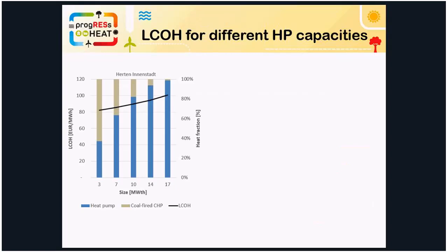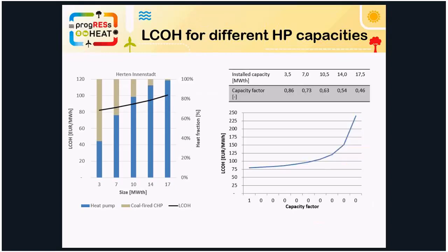We can see that as we increase the size of the heat pump, the levelized cost of heat slightly increases. This is mostly due to the different capacity factors, which have a direct influence on the levelized cost of heat of the heat pump, increasing it by up to 18%. We can see that the heat pump works more efficiently in the region of around 0.7 or 0.8, meaning it should work 70-80% of the maximum time.